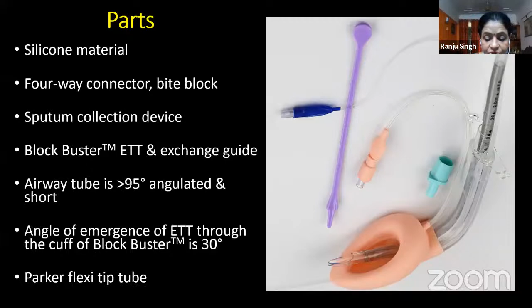Another good feature of the device is the presence of the Parker Flex-Tip tube. This special tube decreases the damage to the structures as the tube passes from the LMA into the glottic opening. So this device may be placed and you may be asked to define its features. You may be asked why it is successful in allowing intubations. You may also be asked subsequently which are the other devices which allow intubation and why this device is more successful. So we've answered most of these questions by now. This is a chart which tells you that through the Blockbuster number 5, an 8 number tube can be negotiated.